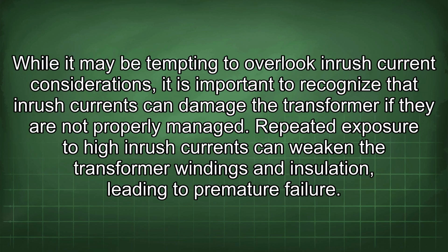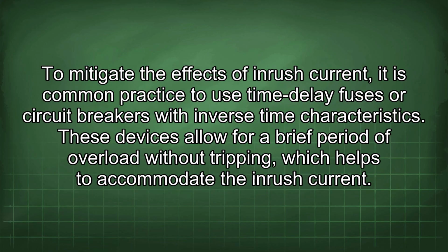While it may be tempting to overlook inrush current considerations, it is important to recognize that inrush currents can damage the transformer if they are not properly managed. Repeated exposure to high inrush currents can weaken the transformer windings and insulation, leading to premature failure. To mitigate the effects of inrush current, it is common practice to use time delay fuses or circuit breakers with inverse time characteristics. These devices allow for a brief period of overload without tripping, which helps to accommodate the inrush current.